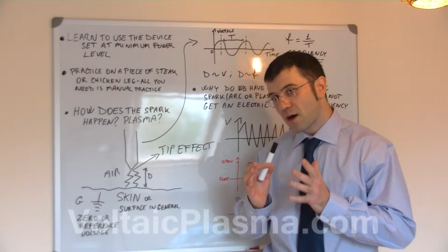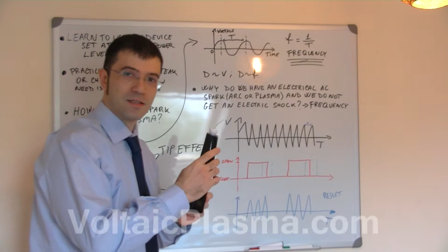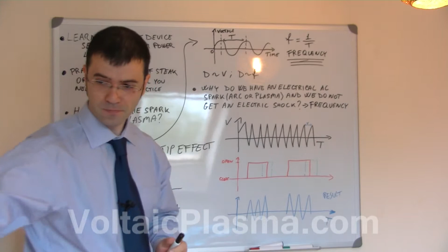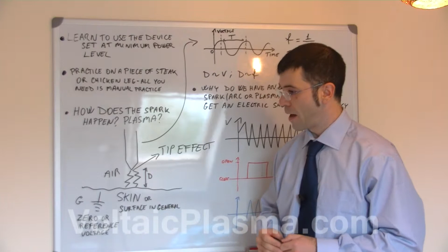So how does this voltaic arc, sometimes called plasma, really work? The principle is very, very simple, and it's been used for many, many years now. Now, let's say I've got here the device, and this is the tip of the device, called the electrode. Now, I have magnified this electrode in here. What we can see is that there is a certain distance that we call D between the tip of the device and the skin or any other surface, because at the end of the day, this same principle applies to many other industries, such as welding, cutting, industrial machining, and so on.